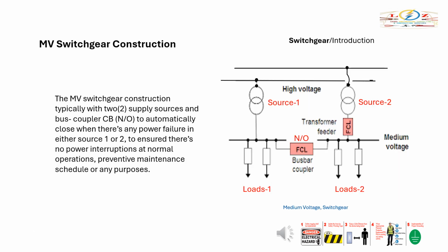The MV switchgear construction is typically with 2 supply sources and bus coupler circuit breaker, CB, N/O, to automatically close when there is any power failure in either source 1 or 2, to ensure there are no power interruptions at normal operations, preventive maintenance schedule, or any purposes.